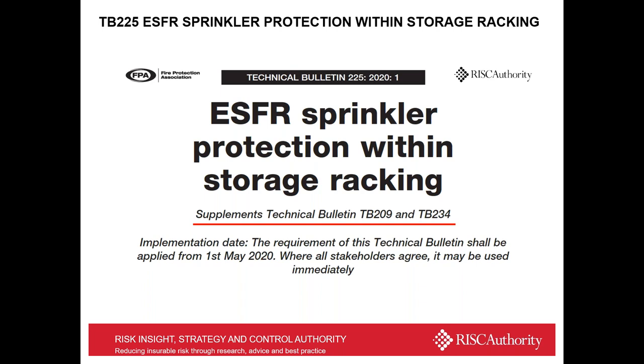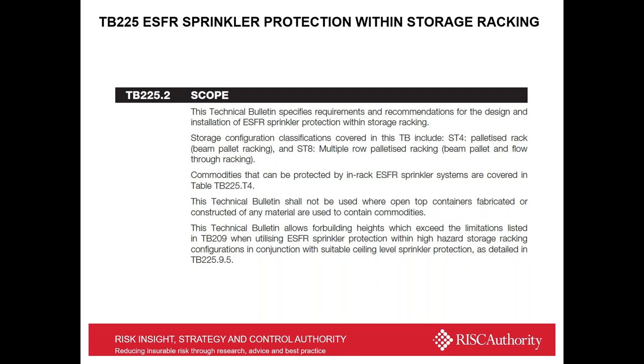And this is based on sprinkler development in the last few years, research into NFPA and FM. The development of TB225 as an ESFR within storage racking was missing from our standards. It's becoming more popular in the UK and being recommended under, obviously, NFPA and FM standards, and the current insurers, members of RISCAuthority, have recognised that we have this area of protection missing following review. Therefore, we've developed this standard, and this standard is strictly in accordance with NFPA and FM following testing that they've done. So we haven't deviated from the requirements of it, but we've included it in TB225.